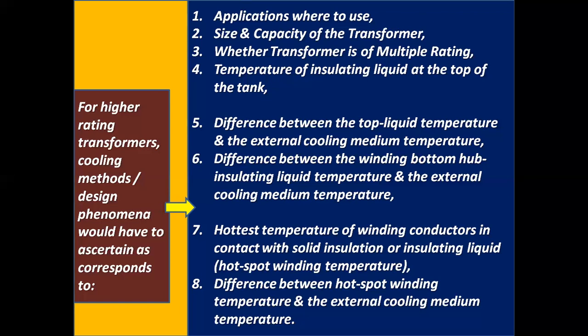Number seven, hottest temperature of winding conductors in contact with solid insulation or insulating liquid, that is hotspot winding temperature. Number eight, difference between hotspot winding temperature and the external cooling medium temperature. These points are to be considered.